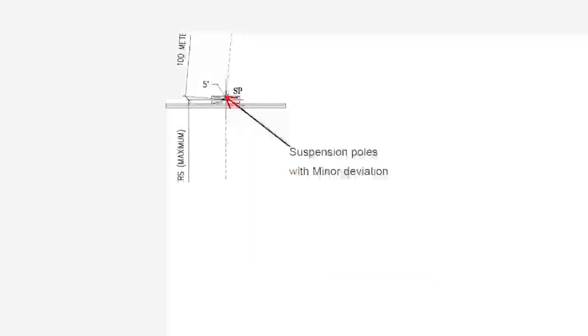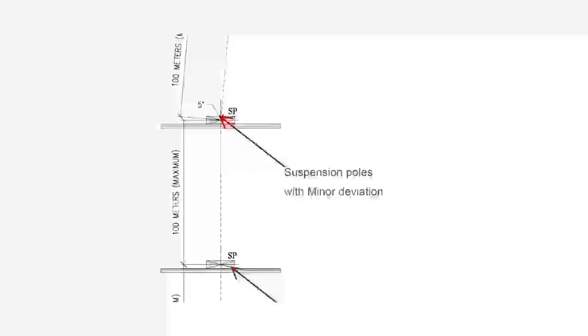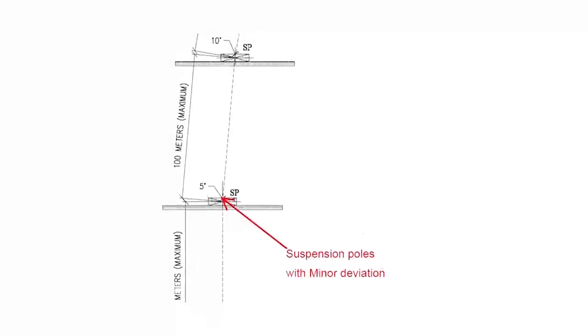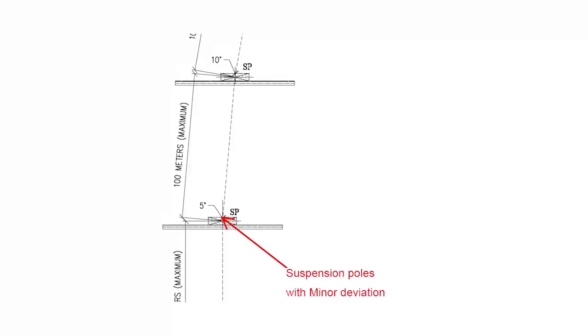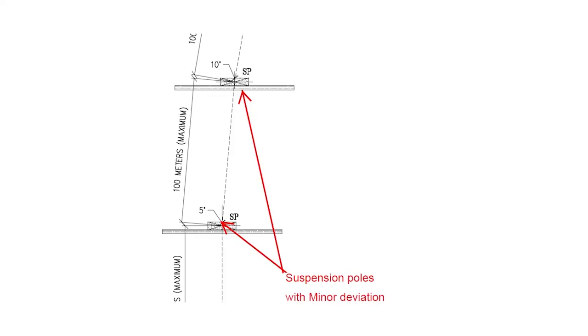Now, next we will try to understand what the angle of deviation is. The route alignment line and the position when it takes a turn, the degree which falls between the route alignment line and the present pole location is called the angle of deviation. In the first pole you can see 5 degrees and in the next pole it is shown as 10 degrees. Now these are all called minor angles of deviation, where you can use the single pole itself.